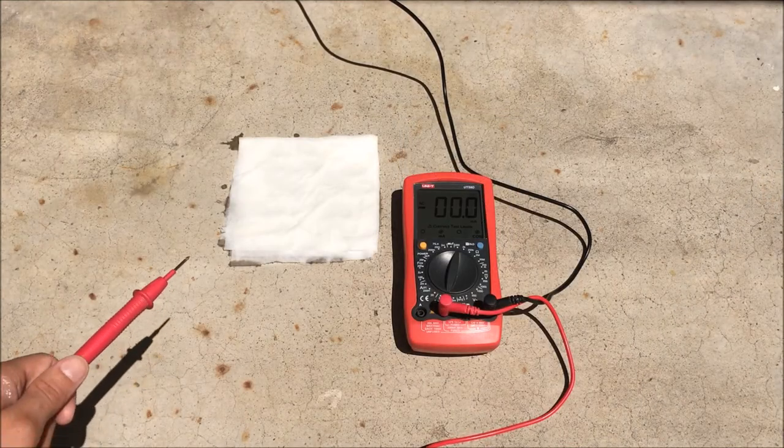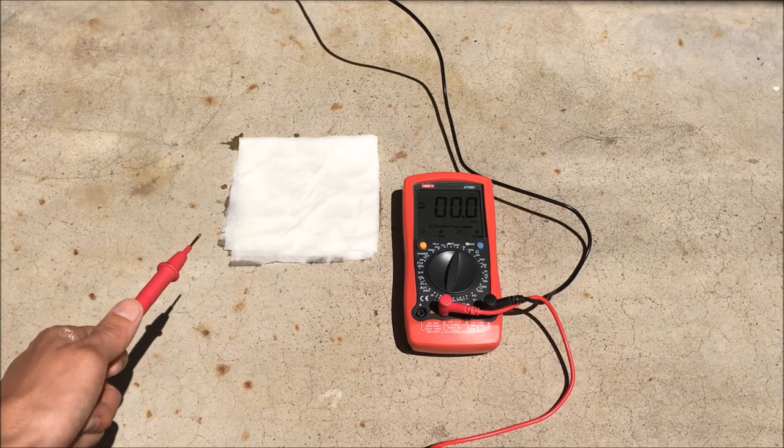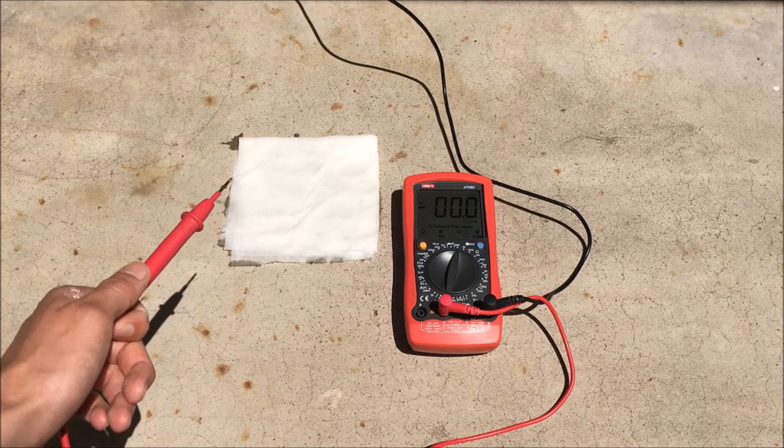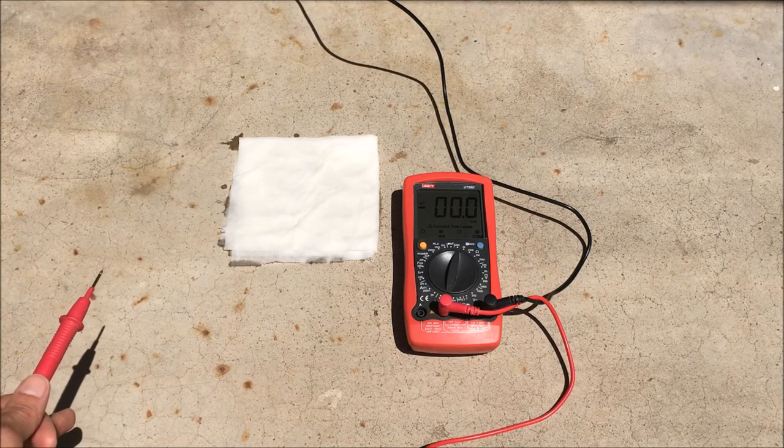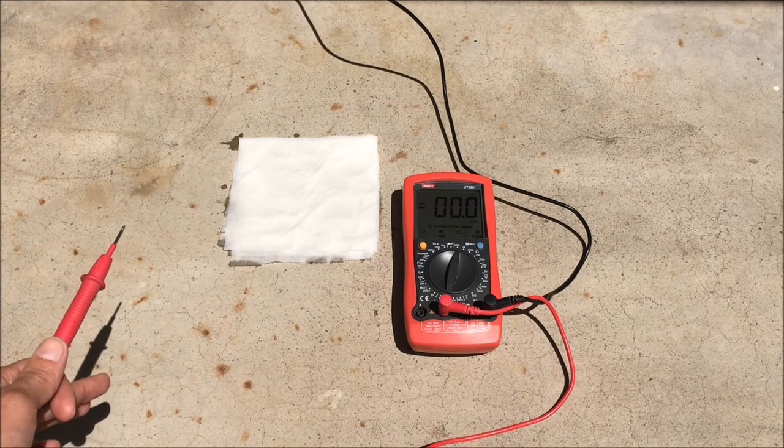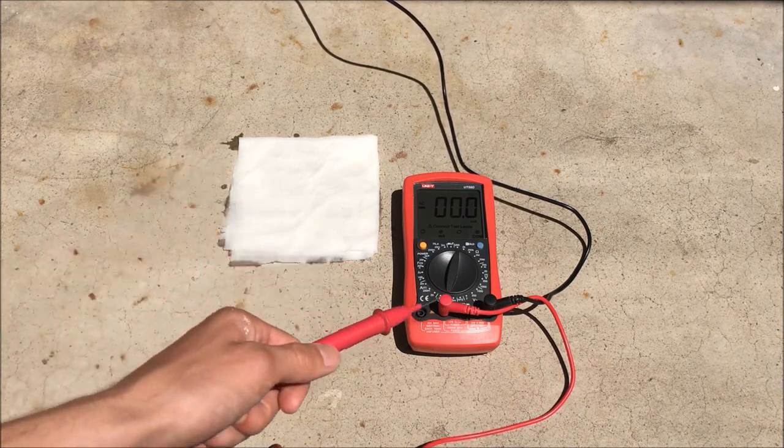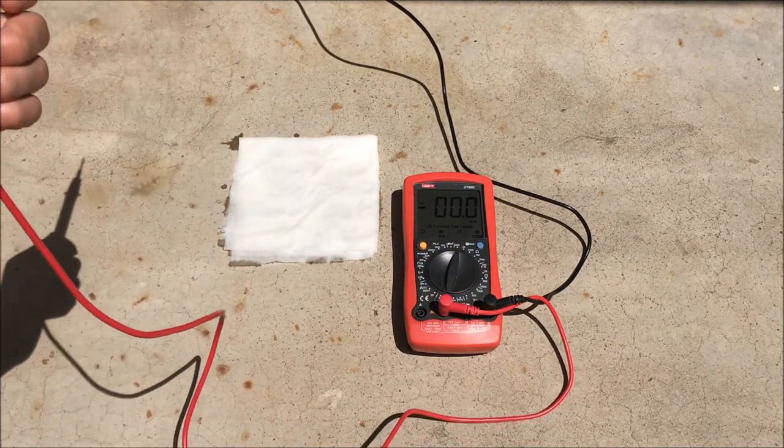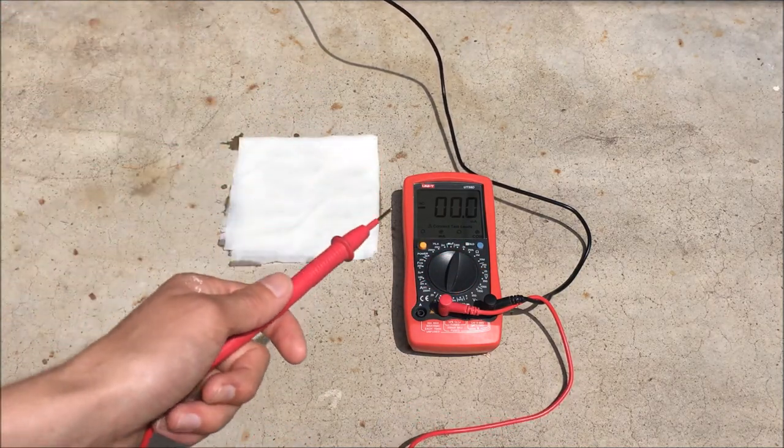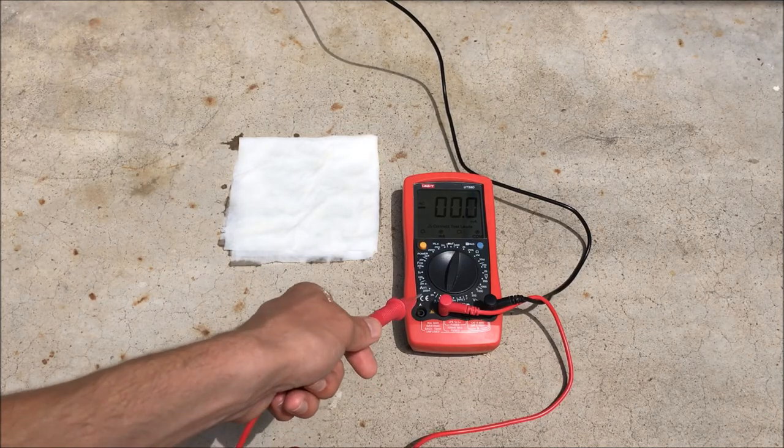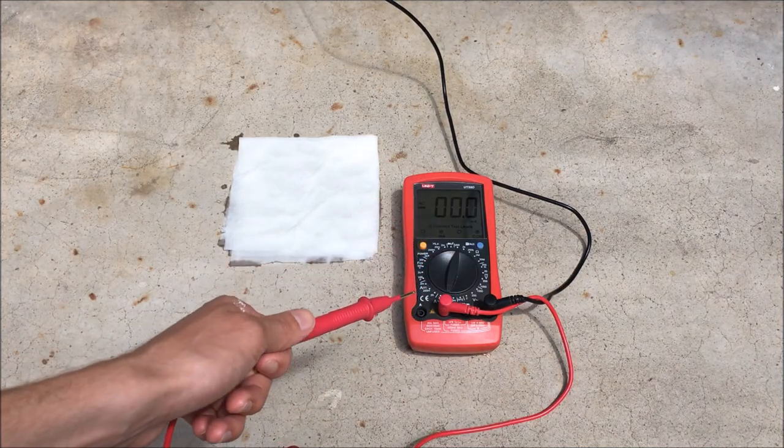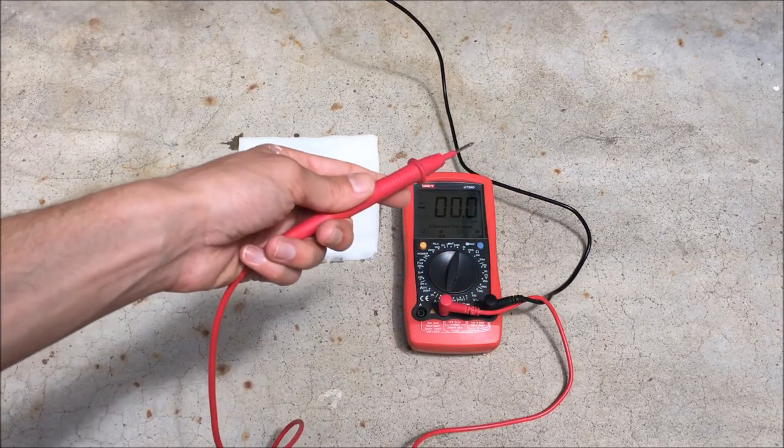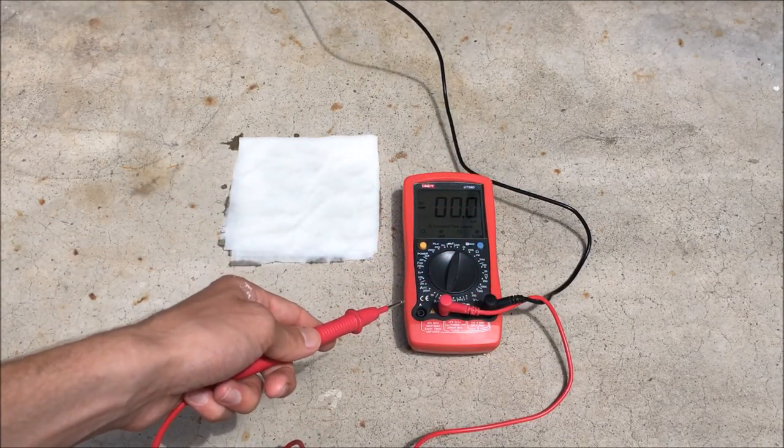We can actually demonstrate this with a multimeter. Here I have set up a wet paper towel that's been soaked in salt water which is an ionic solution and is very conductive, sitting on a concrete slab which is sitting on earth ground. I have the black lead of this multimeter connected to the hot side of an electrical outlet and it's connected on the 200 milliamp range current sense. So that means this plug is directly connected to the black plug through a current sensing resistor.